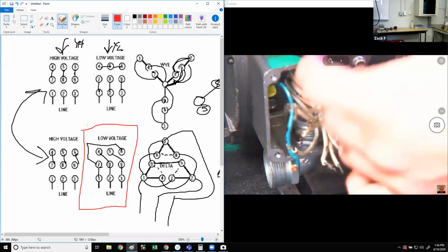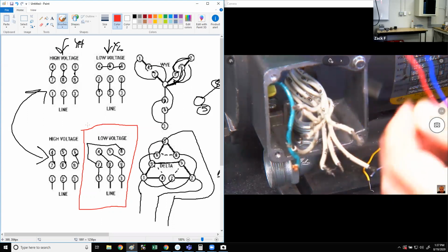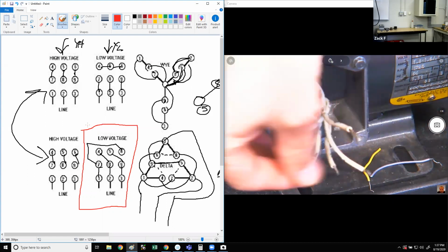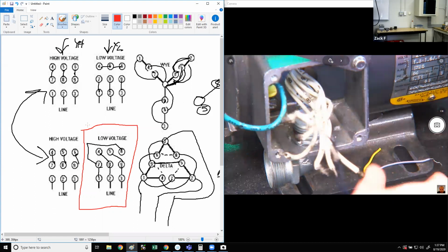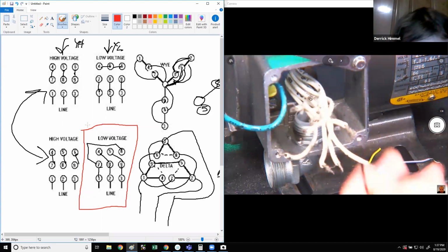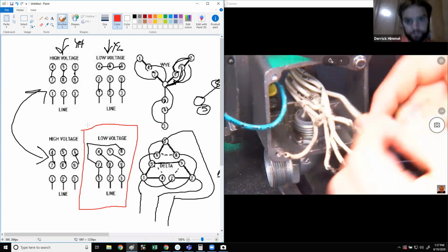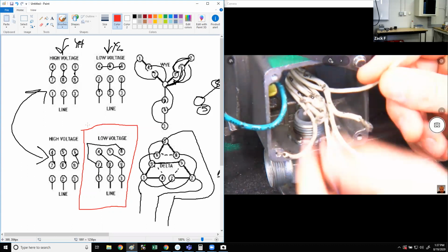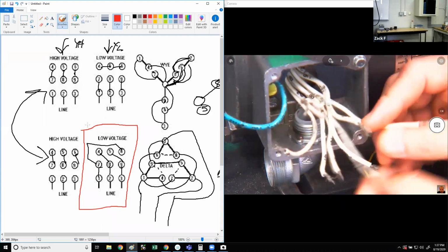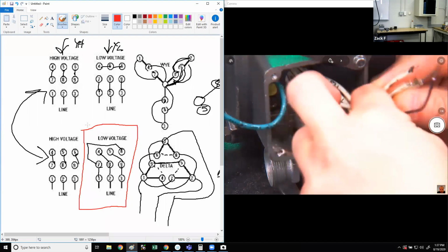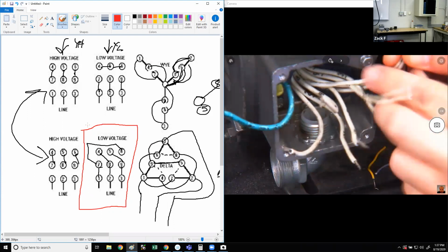All right, so I got black, red, blue coming in. We'll say black is line 1. We're hooking them up delta low. So what are we going to connect here? Got line 1 coming in. What should I do with it? Connected to 7 and 6, I think. Perfect. Yeah. So 1, 7, 6. 1, 7, and 6.